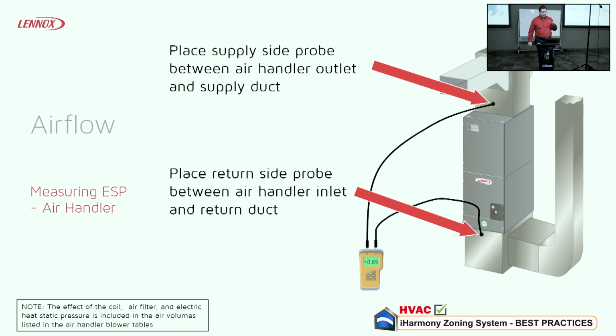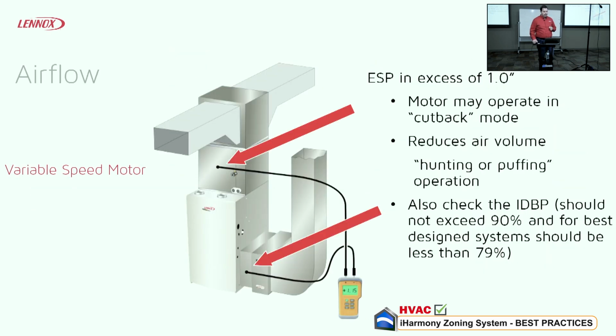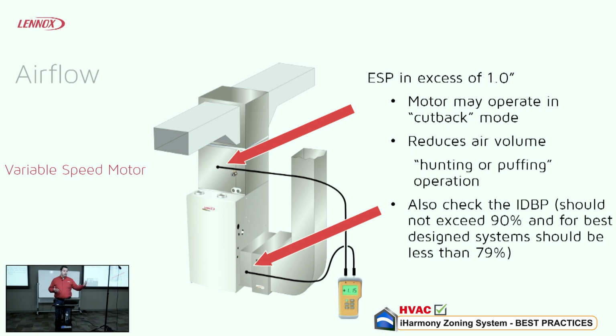And that's really critical on these, is to make sure we don't get cut back, because this will tattletale on you. If it's trying to ramp up and it meets high static, then it's going to throw a code, and that's going to be noisy, and it's going to cause you a lot of heartache there. So the checking that is critical, and also talking about that diagnostic screen.